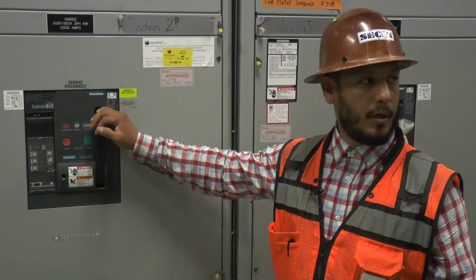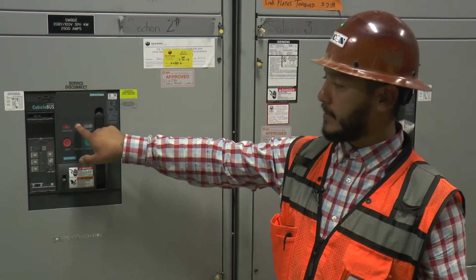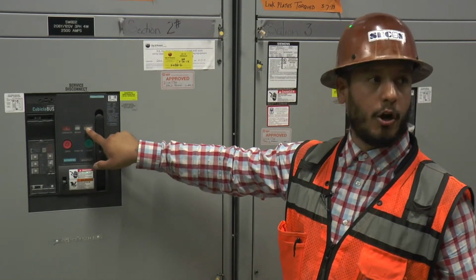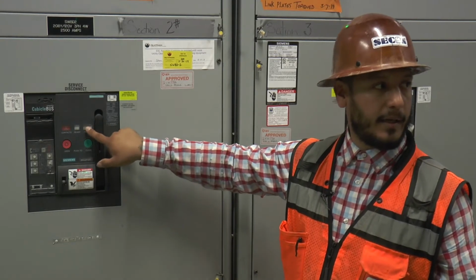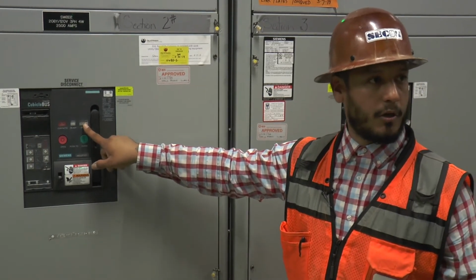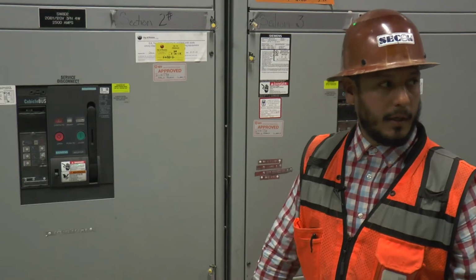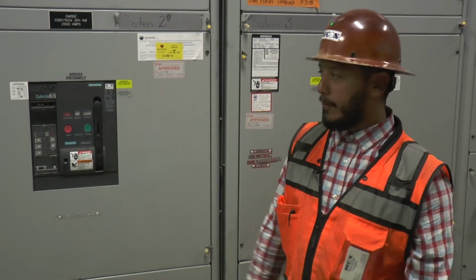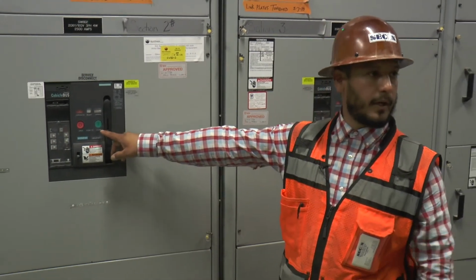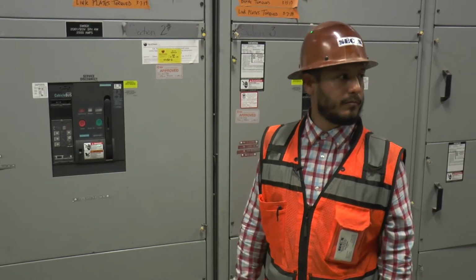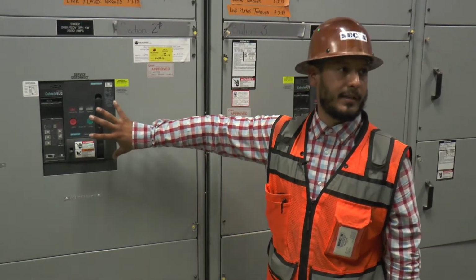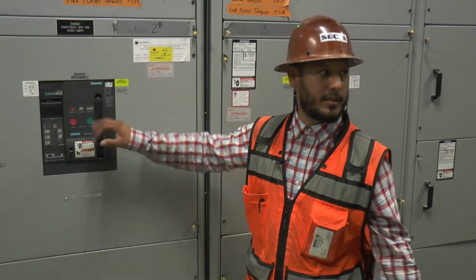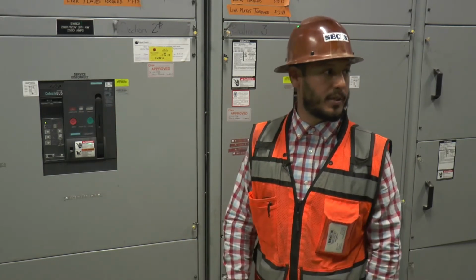Once you're charged, both of these will actually flip. It'll say okay, and this one will say charged. And it'll have a yellow tint behind it as well, letting you know it's charged, ready for you to close the circuit. When you do that, I recommend you kind of look away, just for practice. We've always done that. But this is a very, very intense breaker. Once it's under charge, it just flings right into position.